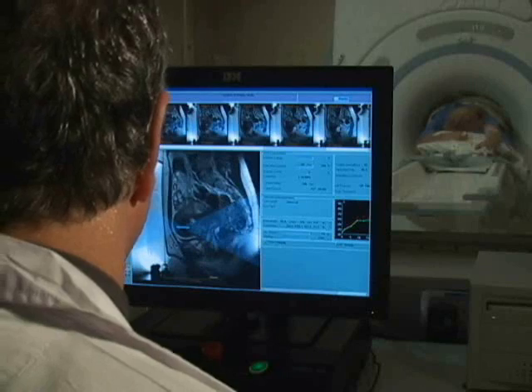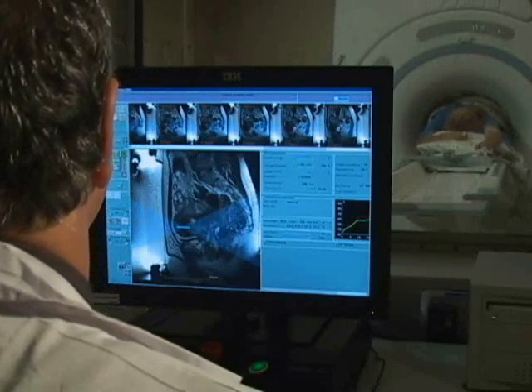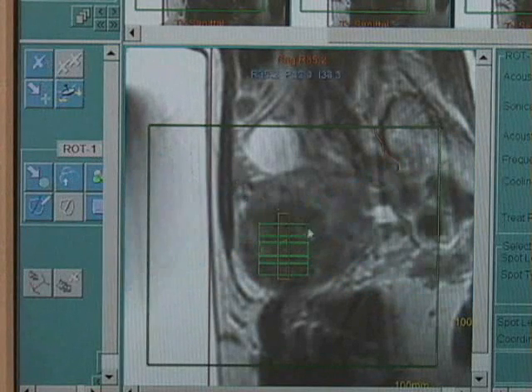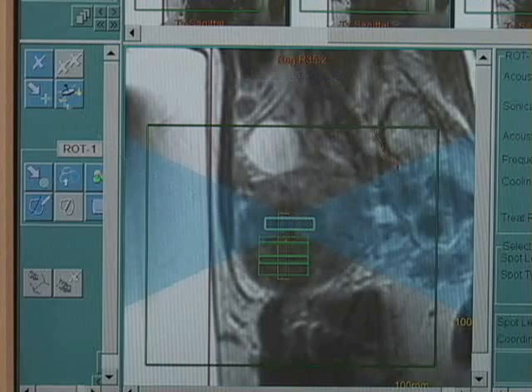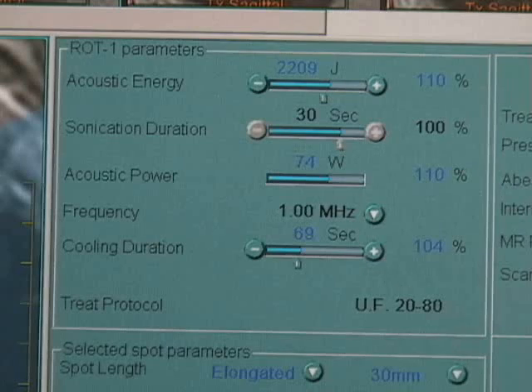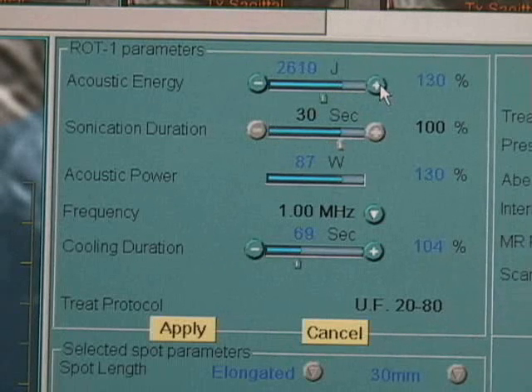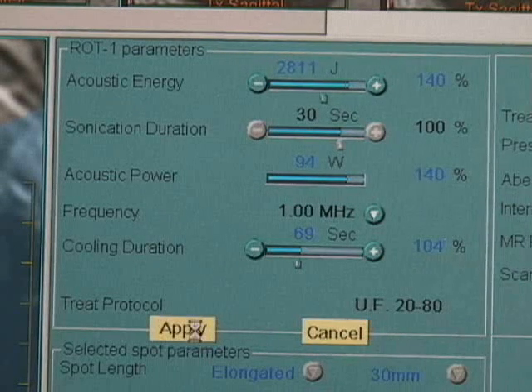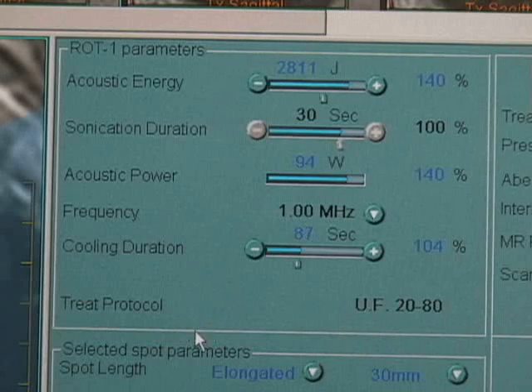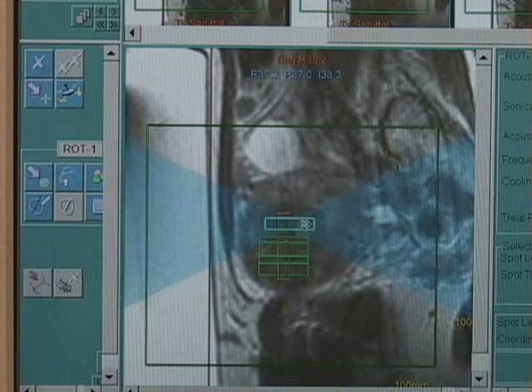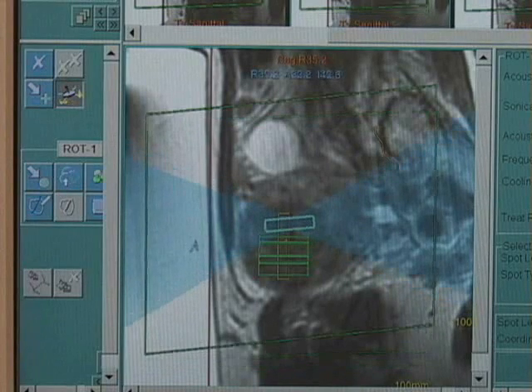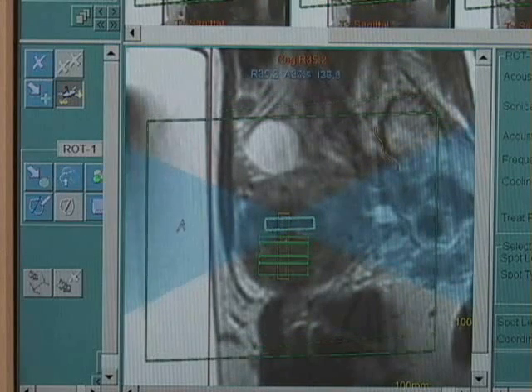Based on the continuous real-time feedback during and after each sonication, the treatment plan can be modified by adding or deleting spots or changing parameters to minimize patient risk or to optimize treatment. For example, if the temperature is too low, the energy can be increased to reach a higher temperature, or, if needed, it can be lowered to reduce the temperature. To avoid sensitive structures in the near or far field, the transducer tilt for that sonication can be modified at any time.